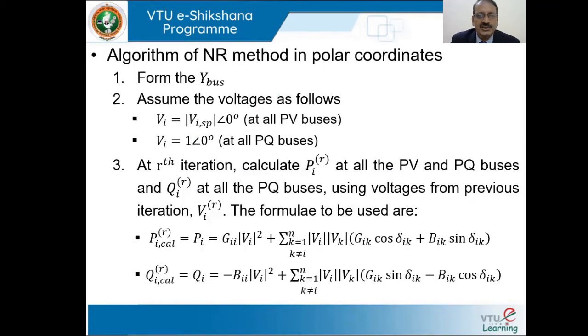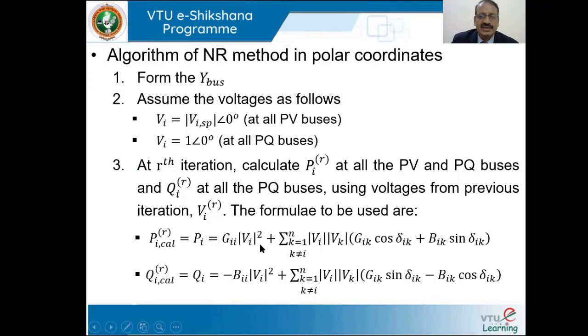After specifying and assuming the voltages at all buses, we need to begin the iterative process. At the R-th iteration, we need to calculate PIR at all the PV and PQ buses and QIR at all the PQ buses. To calculate PIR and QIR, we use the formula: PI calculated at R is equal to GII·VI² plus summation K=1 to N, K≠I, of VI·VK·(GIK·cos(δIK) + BIK·sin(δIK)).